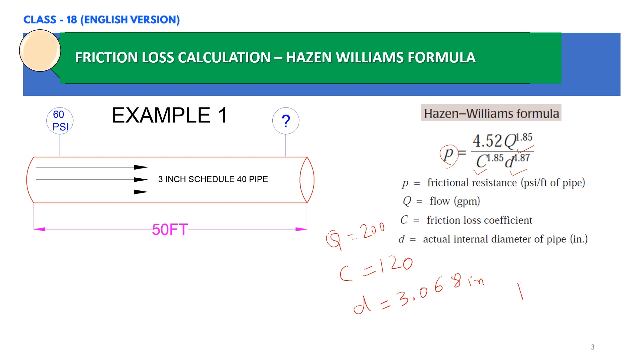So P equals 4.52 times 200 to the power 1.85, divided by 120 to the power 1.85 times 3.068 to the power 4.87. We get approximately 0.049 PSI per foot of pipe. So the friction loss per foot of pipe is 0.049 PSI. The total length of the pipe is 50 feet.